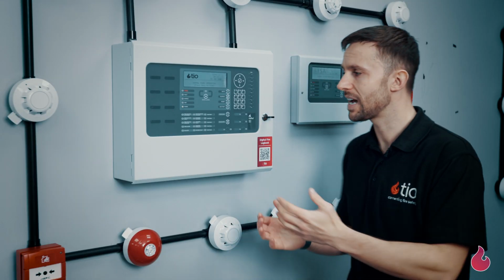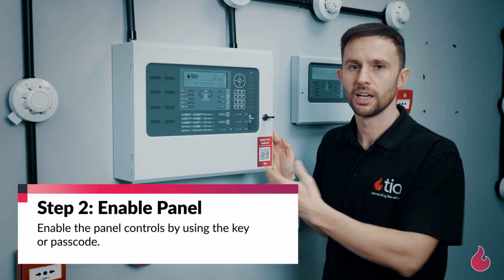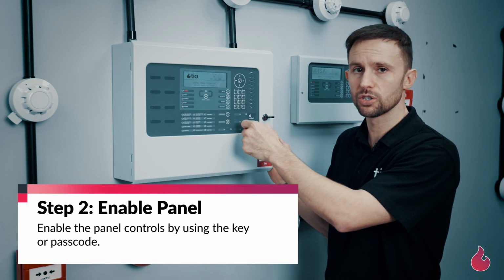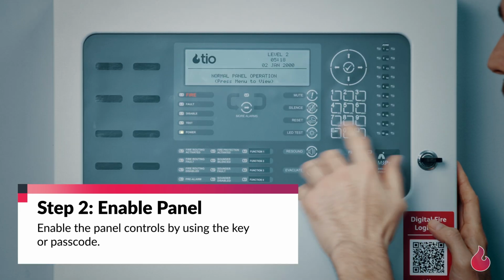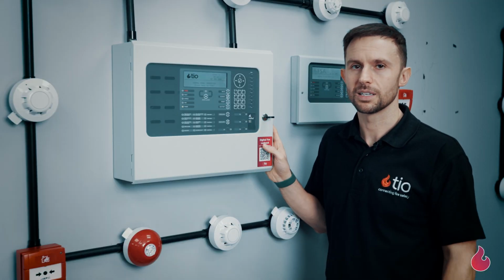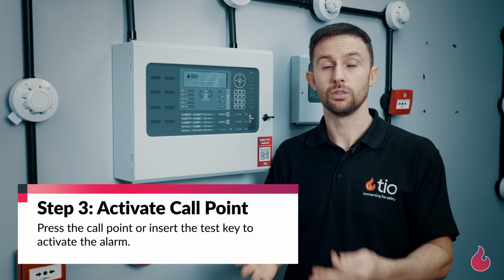Step 2 is to enable your fire alarm control panel. Again, this can be done via a key switch. This particular panel has a code which I've already entered. Once the fire alarm panel is enabled, you then need to check your asset register to understand which call point needs testing. Now I've activated the controls on the fire alarm panel, I can now test my call point.